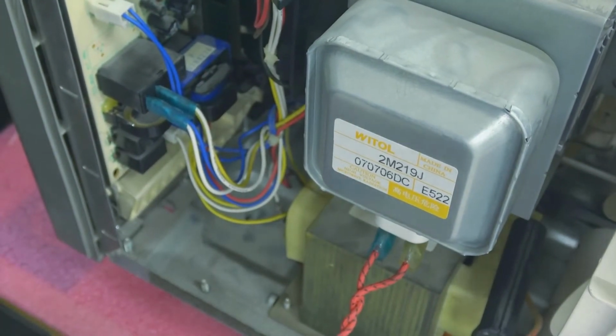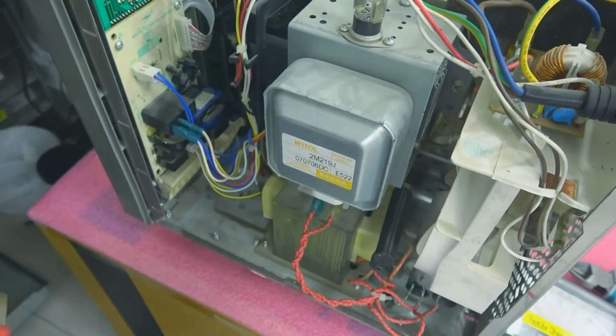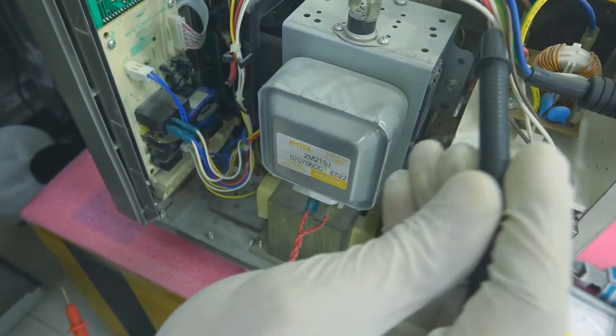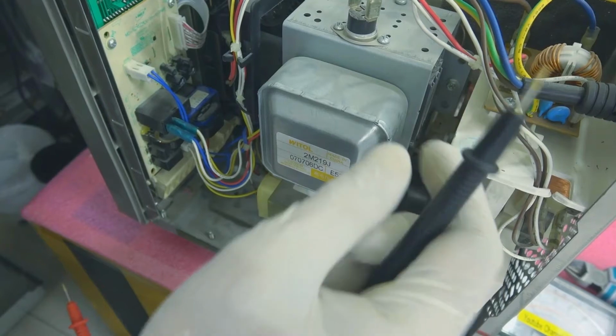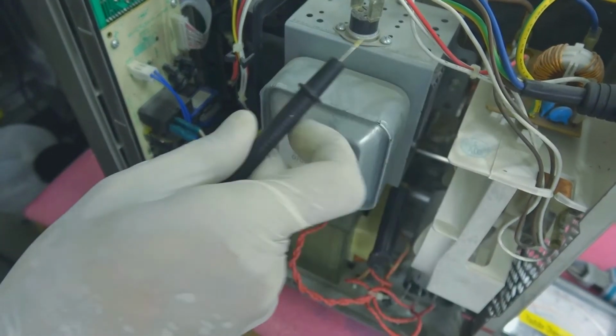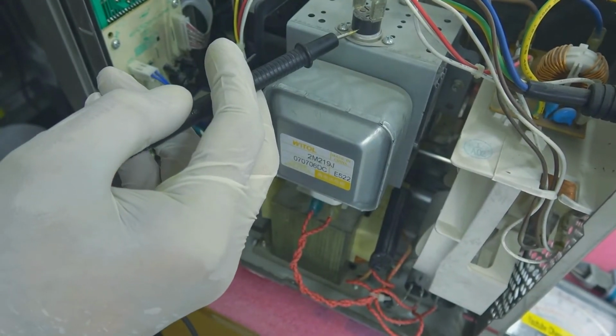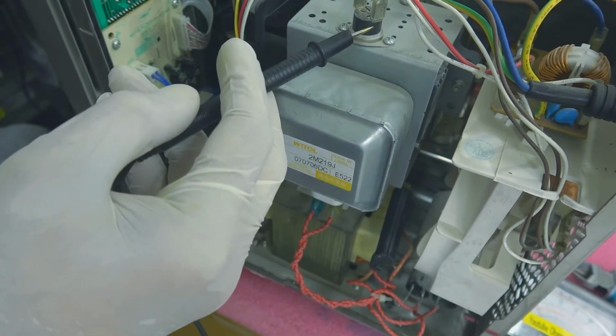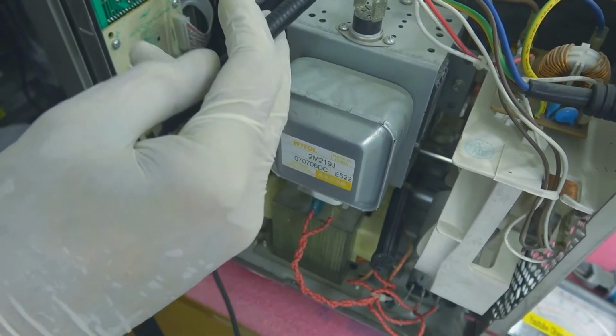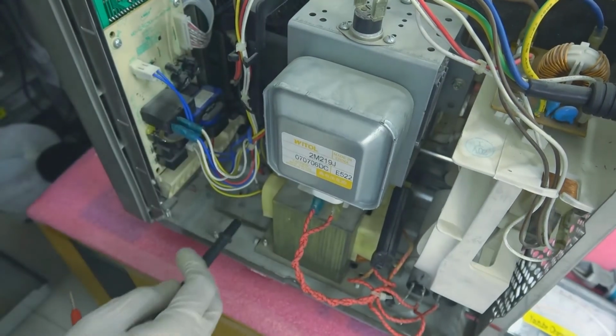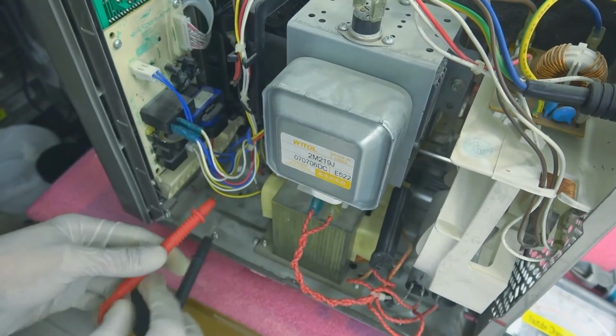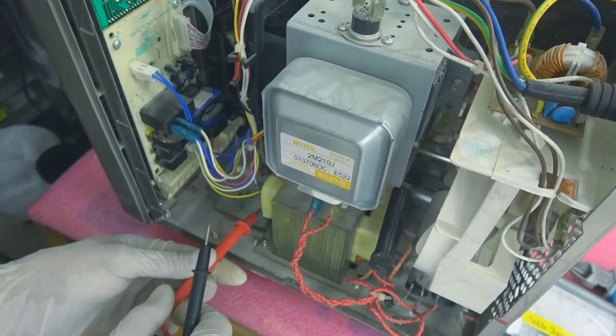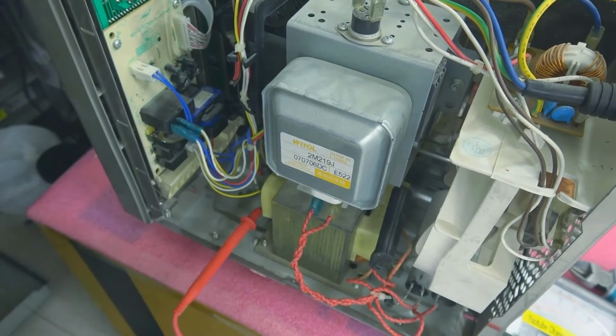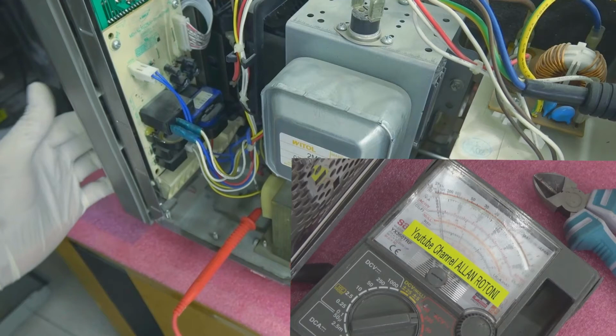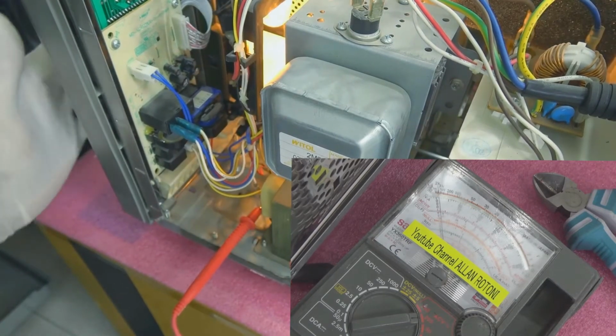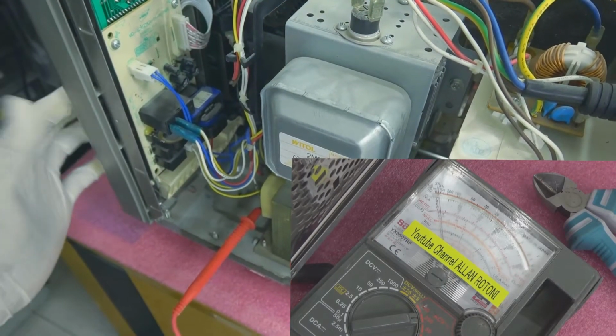But you have to find out first the common line. This is the common line. I already found it, and running to this thermal switch. This thermal switch is good. I already tested it, and main line is here. We're going straight to the high voltage transformer. What I am going to do now is to trace the line. I will turn on the unit again.